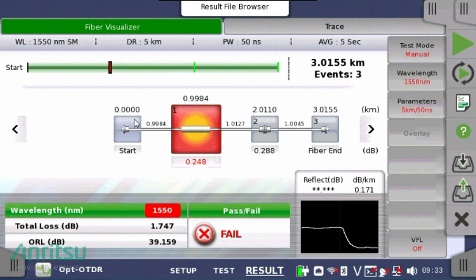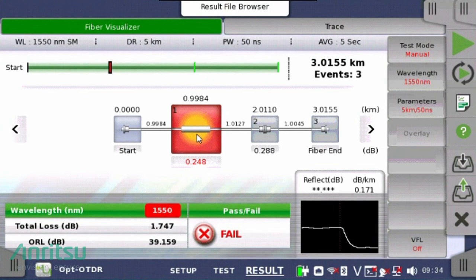Events in blue are passing results; events in red are failing events based on the previously defined pass-fail thresholds. With each event displayed, the distance to the event from the launch point is located above the event, and the amount of loss associated with the event is located below the event. In this example, a failed splice is one kilometer from the launch, with a 0.248 decibel loss for the splice event.